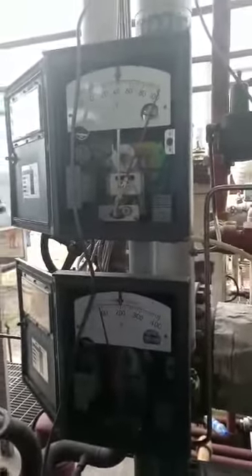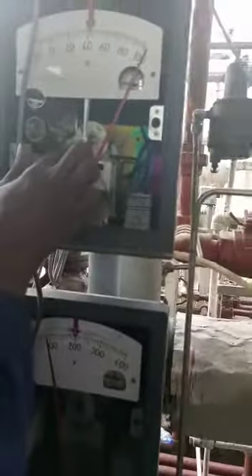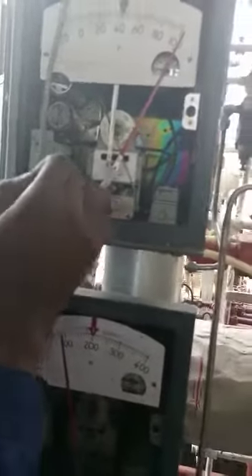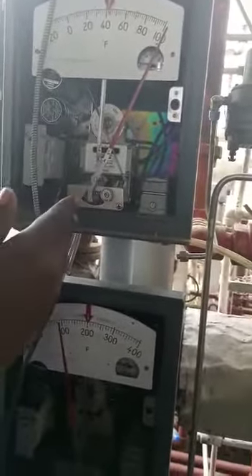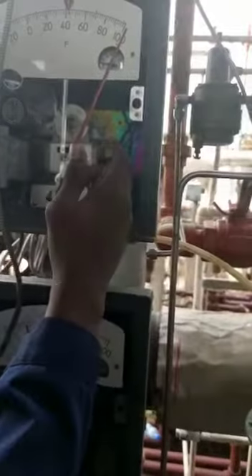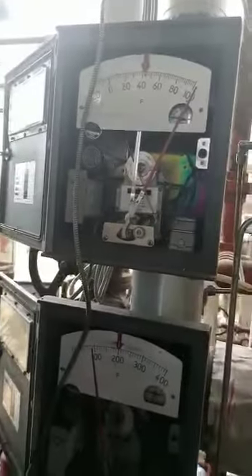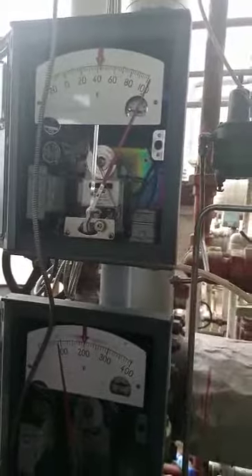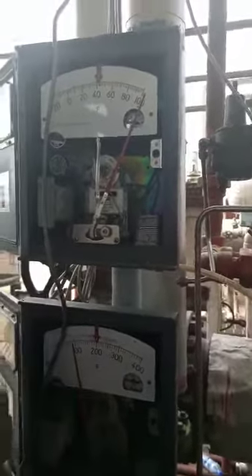first of all, you have to know the make of the controller. This is the Foxboro 43AP FA40N. Now for you to make the adjustment, we have the driven side and we have the driver side, and we have the linking spring, which you can use to adjust it at the 50% level. Then the driven side, which you adjust at 100%. Then the driver, which you use to adjust it at 0%. Now we're going to show you how to adjust the system so that it comes in accordance with the reading you're having at the drive block.